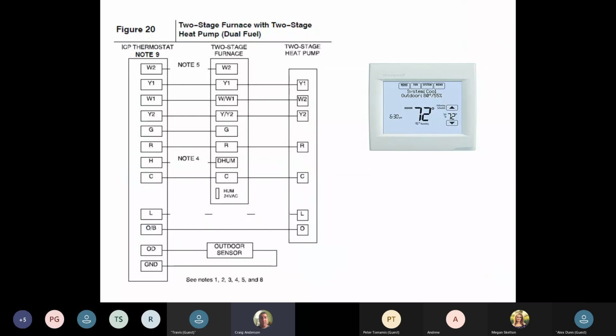So typical wiring, this is just a standard wiring diagram for heat pumps. I always like to throw in there. It pretty much works on everything. It's simple, easy to read. 6 wires to the outdoor unit if you're 2-stage, 5 wires if you're a single stage.